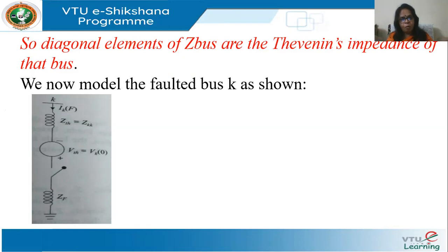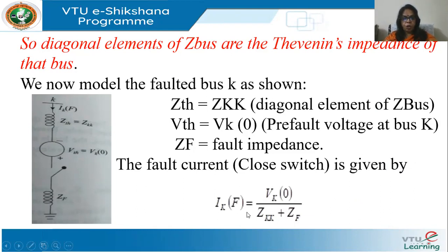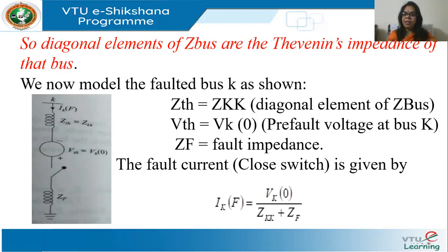This simple beautiful circuit model works for a network of any size — it could be a large grid or a 137-bus IEEE system. When I close the switch to simulate the short circuit, the fault current is I_KF = V_K0 / (Z_KK + Z_F). If Z_F is zero, it simply becomes V_K0 / Z_KK. This is the short circuit current — the fault current. Using this, you can determine what circuit breaker rating should be installed at that particular bus.